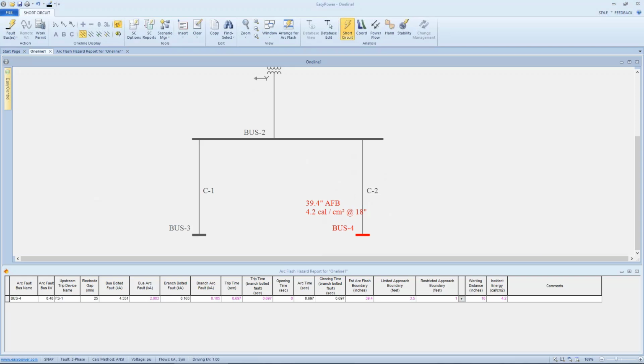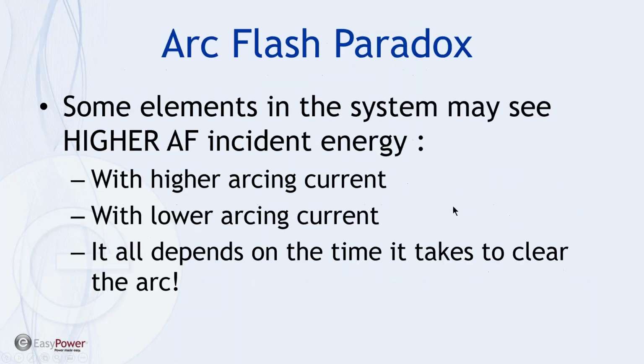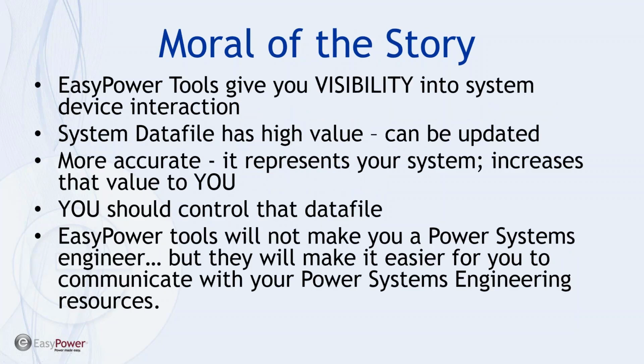And it was this example in this conversation that actually was an epiphany for me, and I better understand that in any given system, I may see higher incident energy with higher arcing current, or I could see higher incident energy with lower arcing current. It all depends on the time it takes to clear the arc. So those of us that think we know everything about Ohm's law may not necessarily understand the true phenomena, which is arc flash. Now, when we start talking about construction of this one-line diagram, you can see just from that example that there's a lot of information in the data file itself, and that's why I emphasize that even if you outsource your study, make sure you get a copy of that data file because it has high value for more than just calculating incident energy.